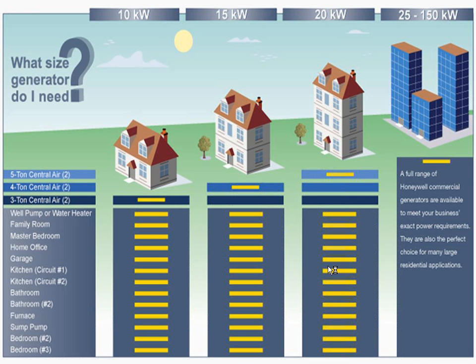So how this breaks down: a 10 kW will start a 3-ton air conditioner, a 15 kW will start a 4-ton air conditioner, and a 20 kW will start a 5-ton air conditioner. There's a 2 after where it says 5-ton or 4-ton air conditioner. All that's saying is you can hook up 2 of those air conditioners, but you're never going to really start 2 of them at the same time. So if you're looking at a 15 kW and they have 2 4-ton air conditioners, just know you'll be able to start only 1 of them, not both.